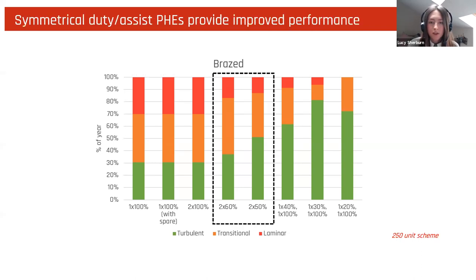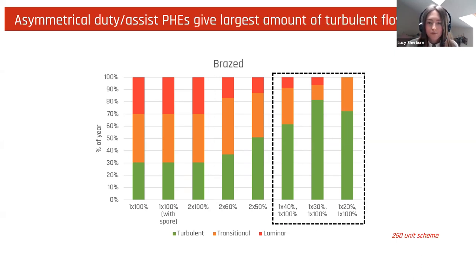Next slide, please. So the symmetrical duty assist plate heat exchangers provided an improved performance. With the two plates sized at 60% or two plates sized at 50%, the laminar flow amount decreased and the amount of turbulent flow increased as well. And next slide, please. We see that the asymmetrical duty assist plate heat exchangers, so those that have the jockey plate, provided the highest amount of turbulent flow and really limited the amounts of laminar flow.